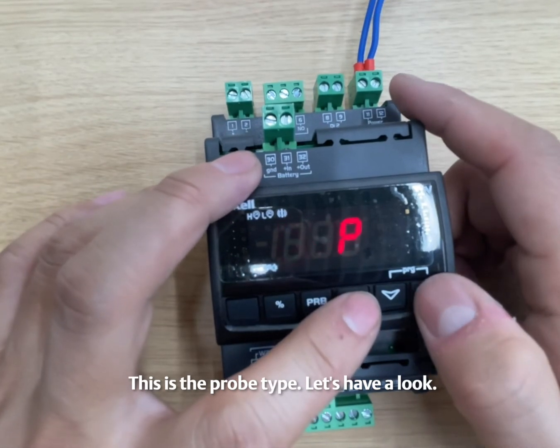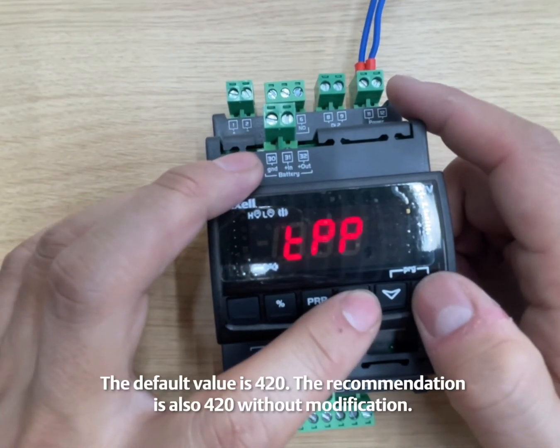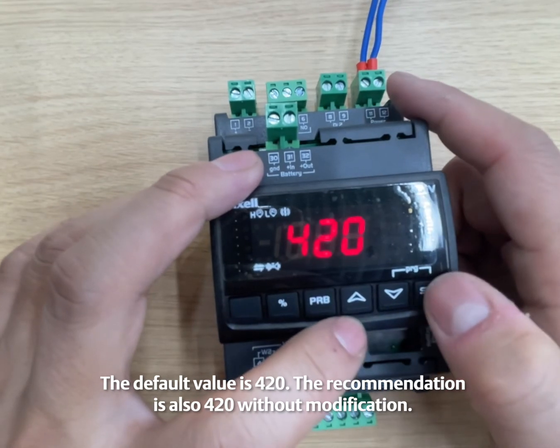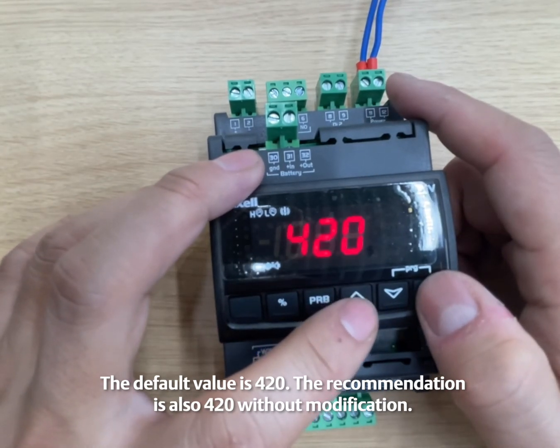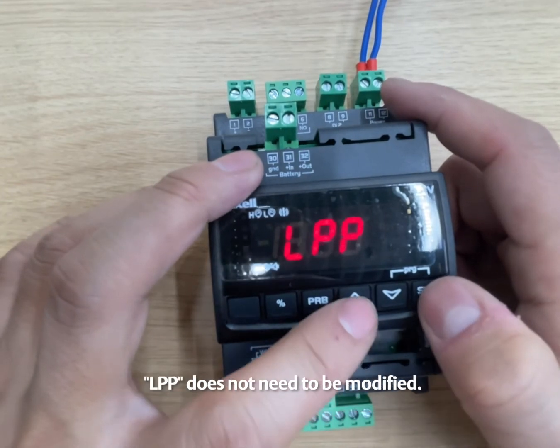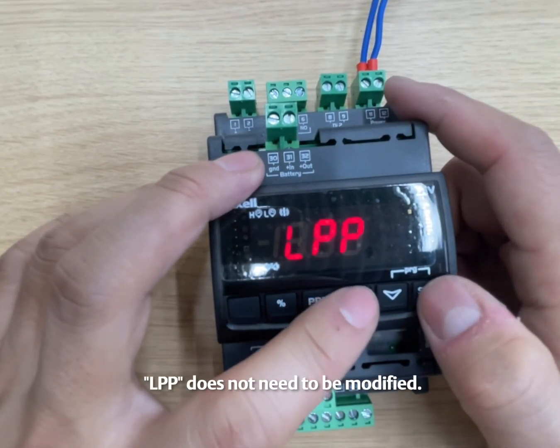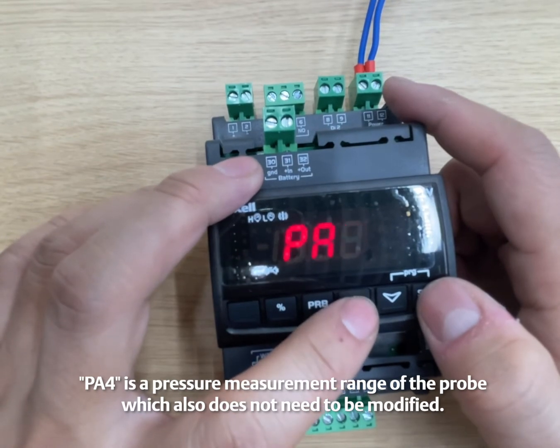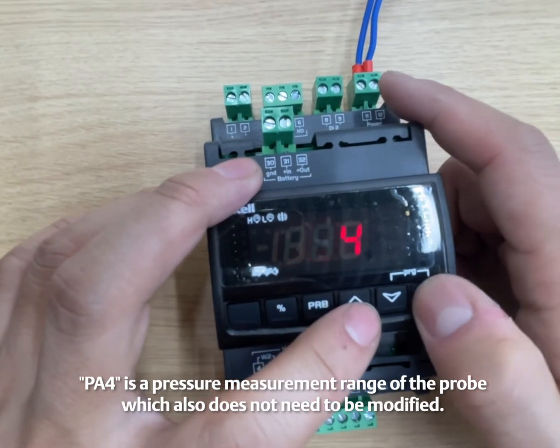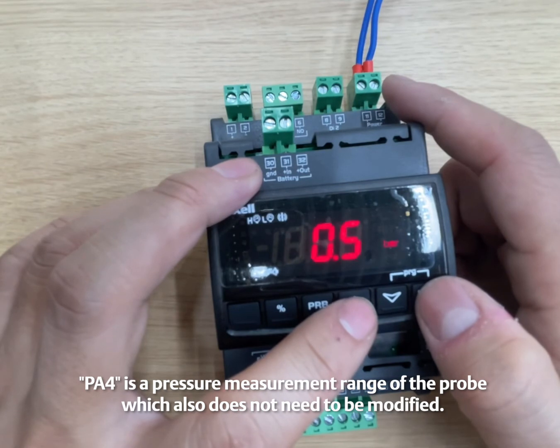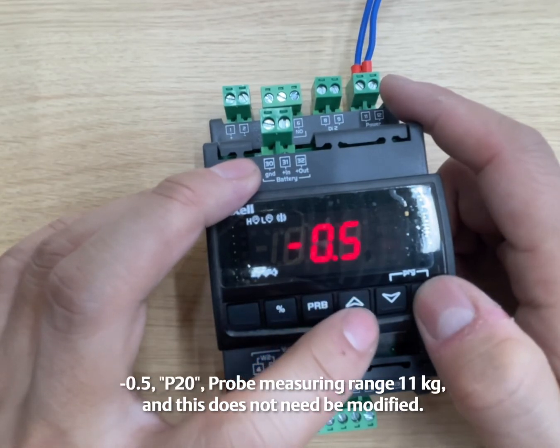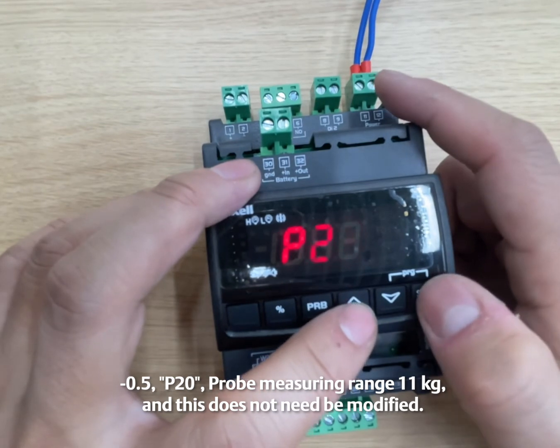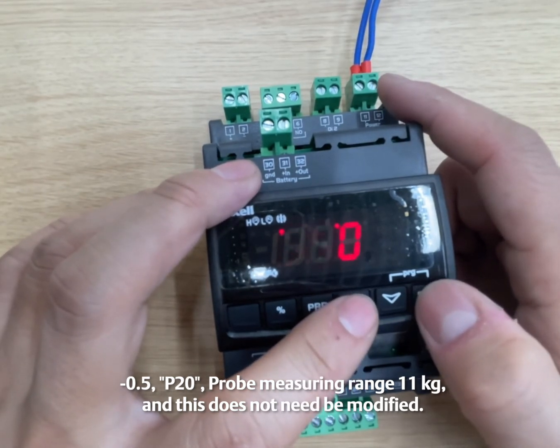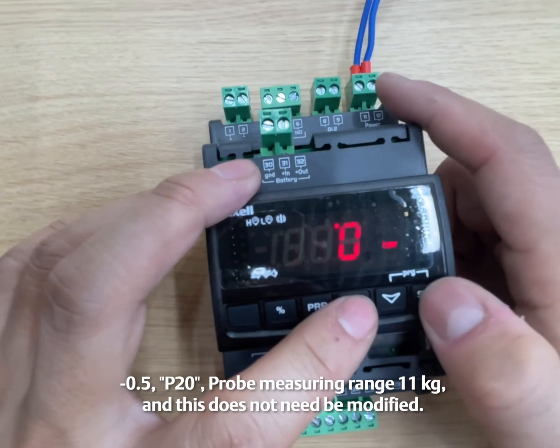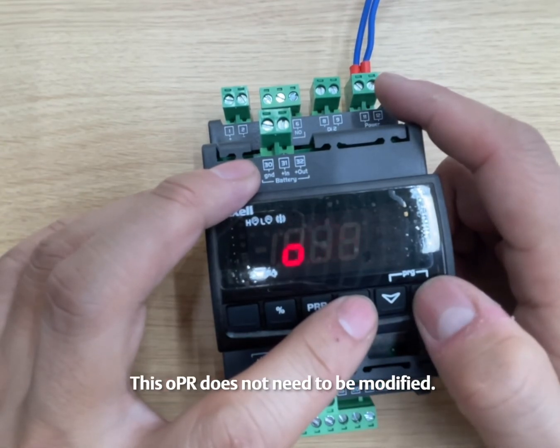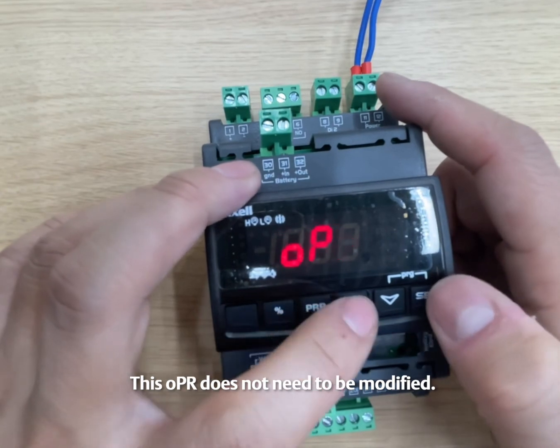This is a probe type. Let's have a look. The default value is 420. The recommendation is also 420 without modification. LPP does not need to be modified. PA4 is a pressure measurement range of the probe, which also does not need to be modified. Negative 0.5, P20, probe measuring range 11 kilograms, and this does not need to be modified. This OPR does not need to be modified.